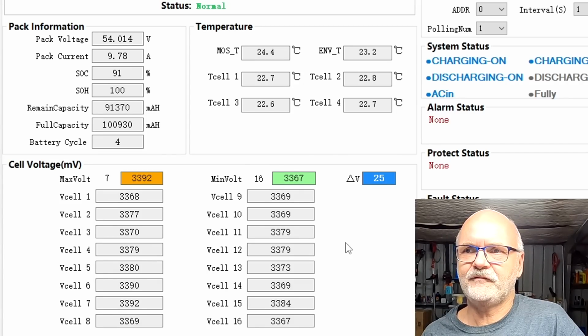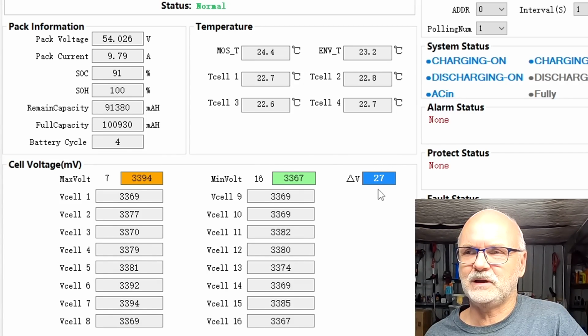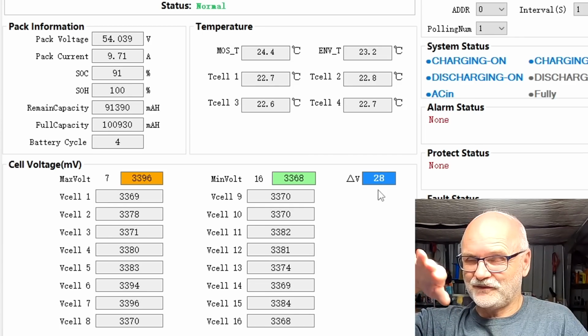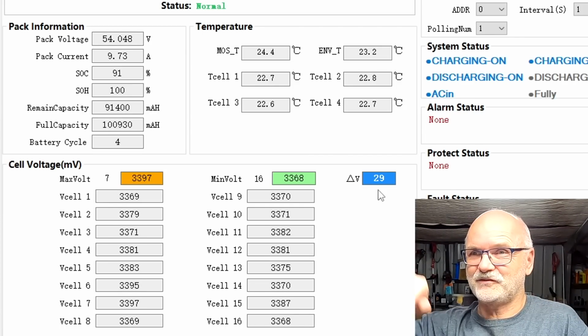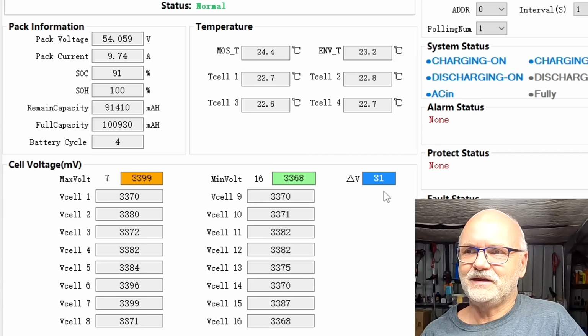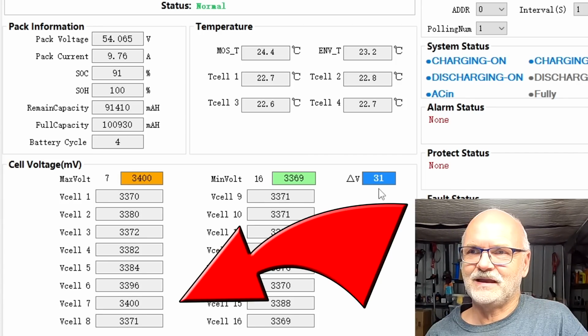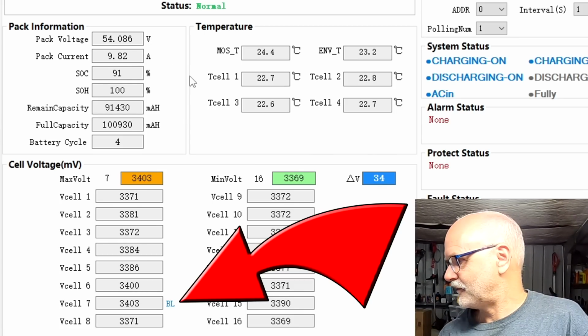All right, we're at 54 volts and the deviation has increased to 26 millivolts. Not too bad, but now we're coming slowly out of the flat area of the curve into the knee, and the deviation is increasing fast as the voltage rises to 55. Still charging with 10 amps.